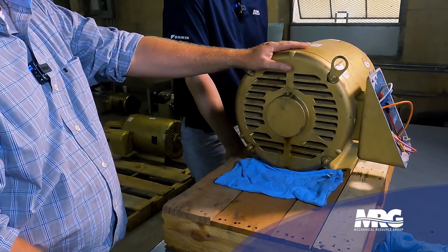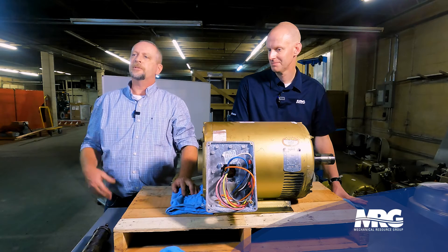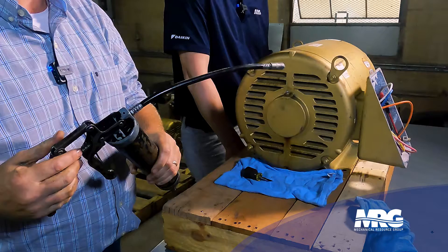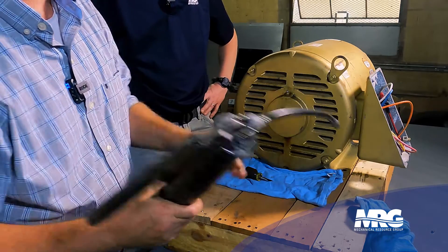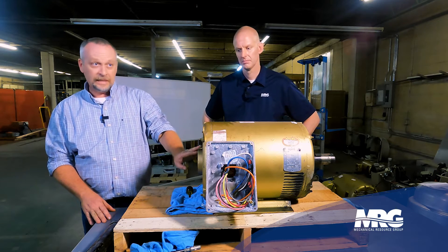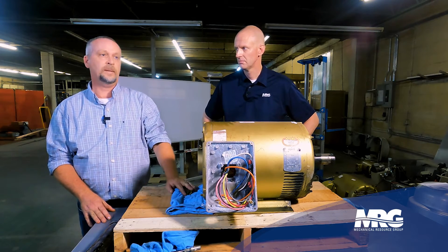That's probably the reason this one failed as well. You'll hear a lot of different things from motor manufacturers — grease them every six months, grease them every year, put this much grease. I've got a grease gun here, and I could do a lot of research to figure out how much grease comes out per squeeze. But we're going to talk about the easiest real-world way to do it, so when you walk away you have the proper amount of grease in it and you've gotten all the old grease out — no question about it.